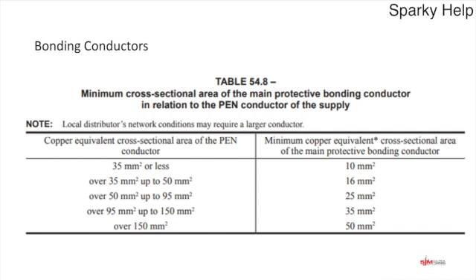For this one then, bonding conductors, minimum cross-sectional area of the main protective bonding conductor in relation to the PEN conductor. That's protective earth and neutral, that's the outer sheath, the braided bit around the outside of the supply authority's cable. And what that basically says is if it's 35mm or less as its equivalent size, then the protective bonding conductors would be 10mm, and that's fairly standard for most domestic installations in the UK.